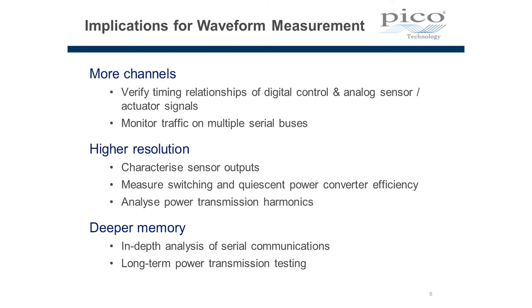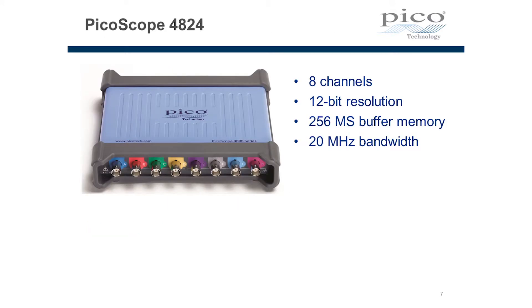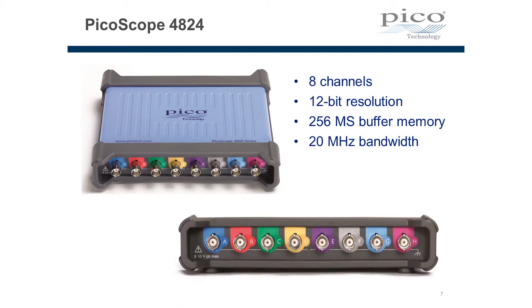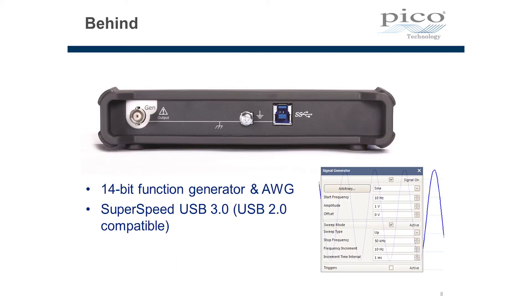Deep memory is something that enables that kind of measurement. The Picoscope 4824 is the first measurement device in its class to offer 8 channels with 12 bits of vertical resolution, deep buffer memory with 256 mega samples, and 20 megahertz bandwidth. On the front panel we have each of the 8 input channels, and on the rear panel we have an additional arbitrary waveform generator and function generator, and the connection to a USB 3 interface which gives the communications interface to the host computer as well as power to the scope itself.